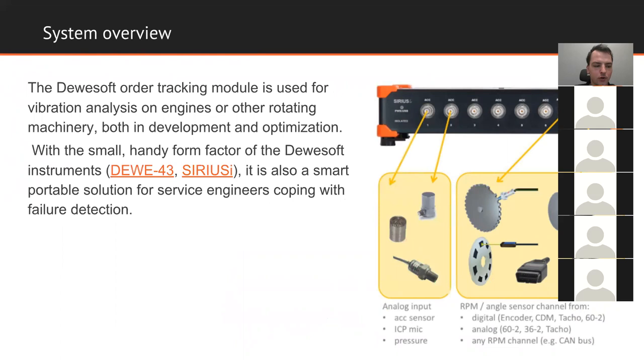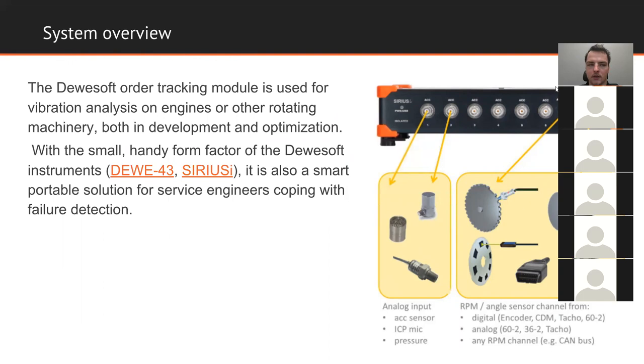To perform order tracking, we need to measure vibrations of the machine and the rotational frequency. Depending on what we want to analyze, acceleration sensors or microphones are connected to analog inputs. If they are voltage or ICP type, they are connected to the SIRIUS ACC module. The angle sensor can be connected to the counter amplifier — possibilities include an encoder with individual pulse count, a tape sensor with black and white strips, a simple tacho with one pulse per revolution, or a gear tooth sensor like a 60-minus-two wheel sensor.